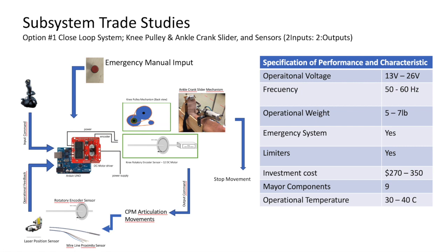Additionally, we have a second input point provided by a manual emergency button. The purpose of the button is to provide immediate cessation of device activities to maintain patient safety and protection.